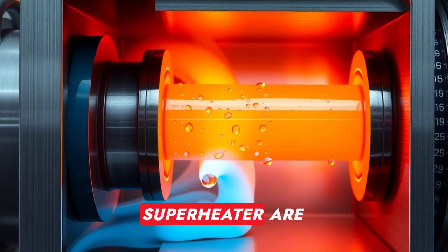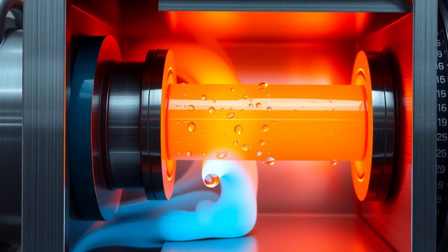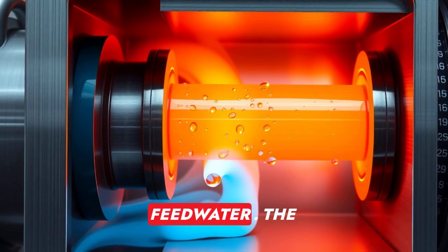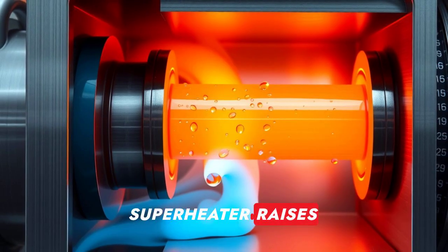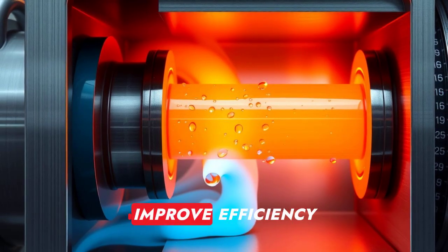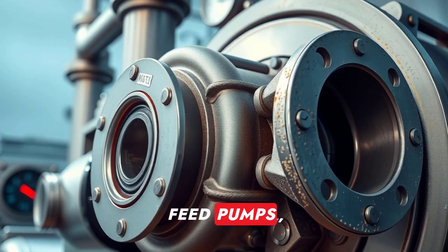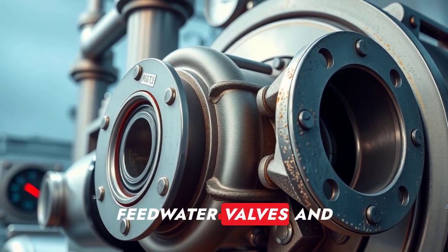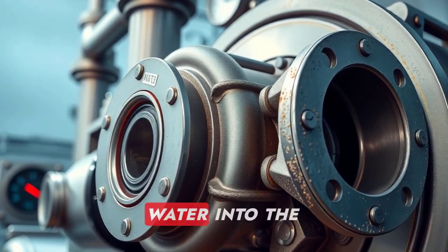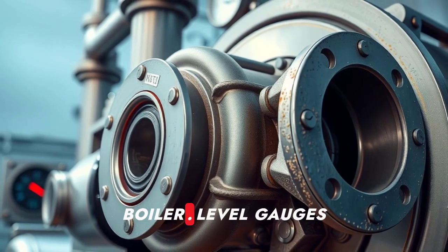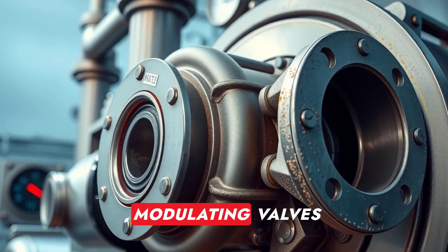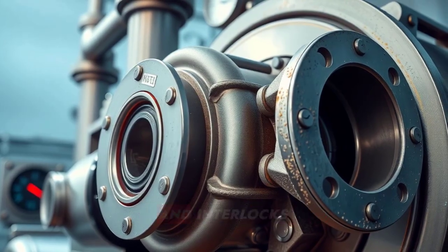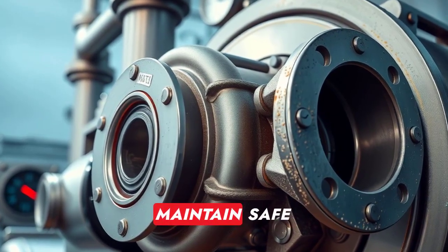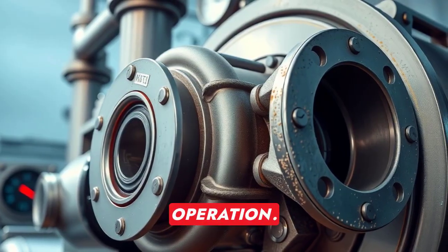Economizer and superheater are integral. The economizer preheats feed water. The superheater raises steam temperature to improve efficiency and dryness fraction. Feed pumps, feed water valves, and traps transfer water into the boiler. Level gauges, modulating valves, and interlocks maintain safe operation.